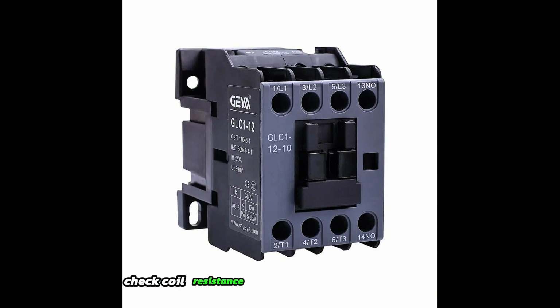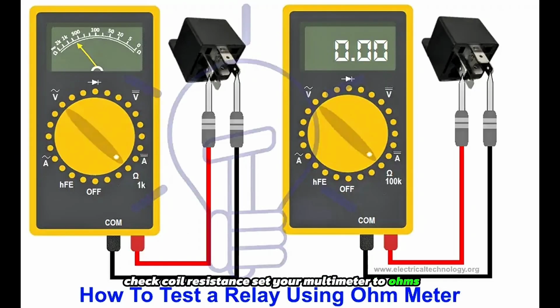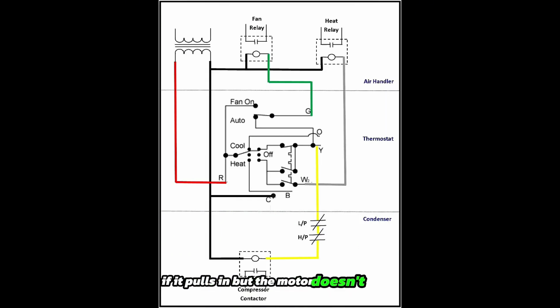Check coil resistance. Set your multimeter to ohms. Measure between the two small terminals, usually marked A1 and A2. Typical resistance is 10 to 30 ohms. If you read OL or 0, the coil is bad. Apply 24 volts manually. You should hear a click and see the contacts pull in. If nothing happens, bad coil. If it pulls in but the motor doesn't run, check the high voltage circuit.